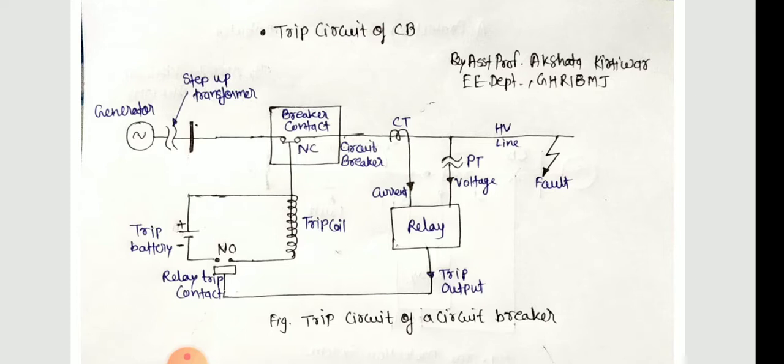The relay output contact is wired in series with the trip battery as you can see in the figure, as well as with the trip coil. Thus, when the relay operates, the trip coil gets energized and the circuit breaker quickly parts its contact.